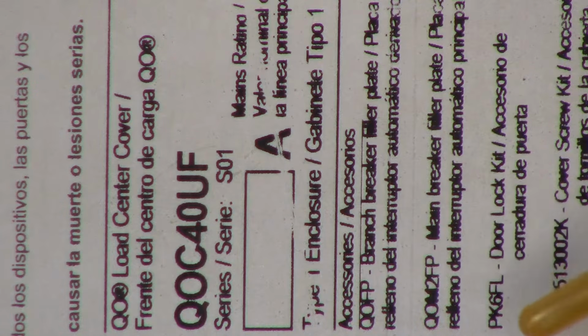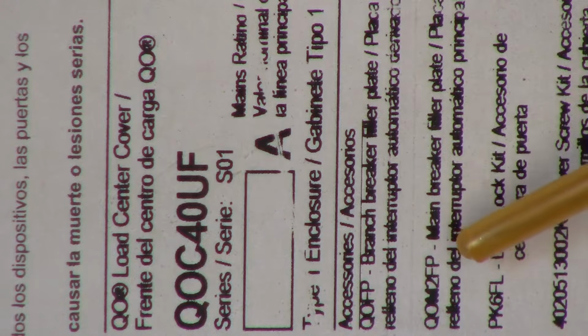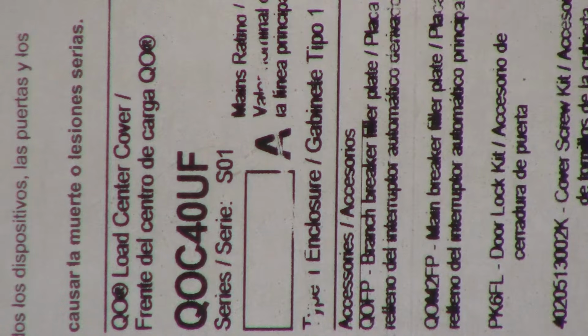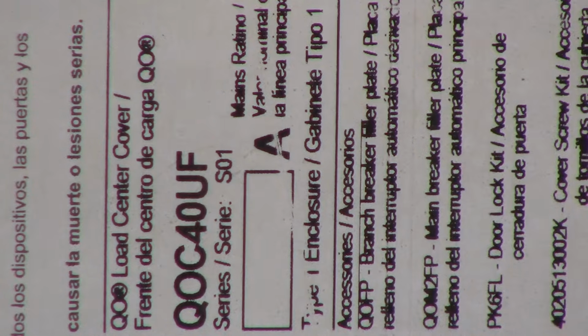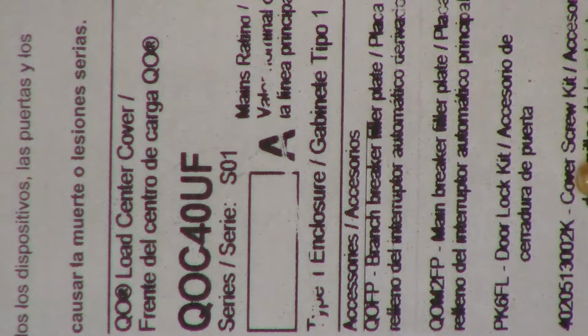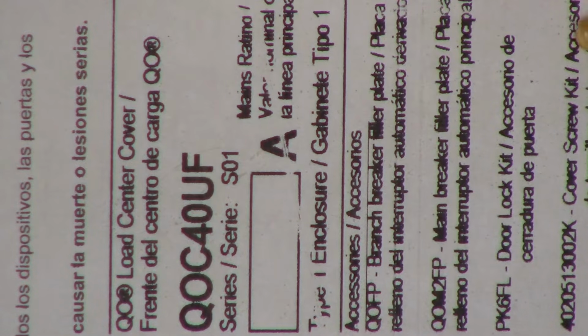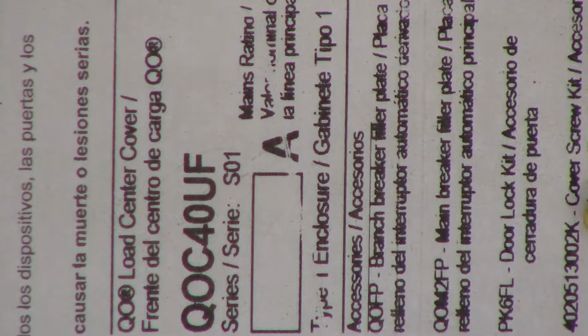Also down here it tells you the model number for the main breaker filler plate, if you had to fill this plate here at the top for the main breaker, if somebody had knocked out the actual tab on it and you're using it as a main lug only. It tells you the type of filler that you would need for it. It has all that. It has a door lock kit number on here. Here's the other one here. This one here, you see it. This actually tells you the cover screws. So there's a kit that you can buy, and it tells you the model number, and these are the type blunt screws that go for this panel cover. Okay, so you get a lot of information here.